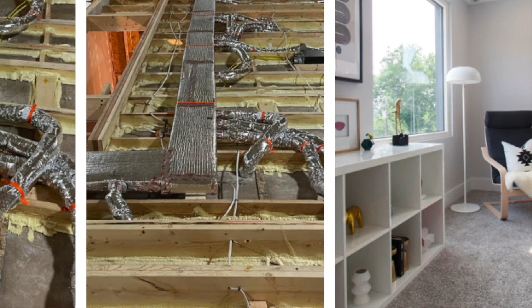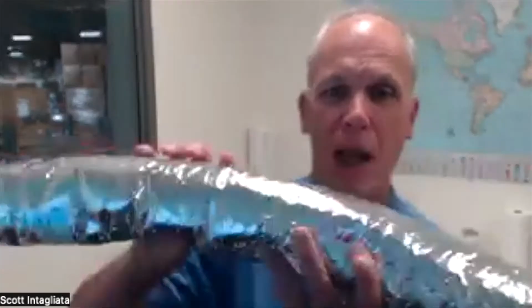And so typically it's an interstitial. Typically we're using a flat duct. And because we use half the volume of air, that flat duct will deliver up to 3.5 tons of capacity. So it fits into a tighter space. It's 3.5 inches outer diameter. It's flexible. It's highly insulated. You'll have less than 1% thermal loss with our ducting. Conventional ducts are going to lose 20 or 30% of their thermal energy. With Unico, you don't have that.